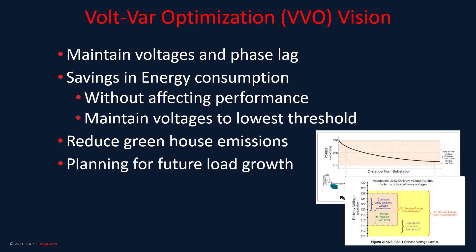The concept of VVO and CVR is to maintain voltages and phase lag within certain limits or specified values by using tap changers or by reactive power injection. These voltage limits or specific voltages at various locations in the distribution system are calculated using optimization of the mathematical models of the system.